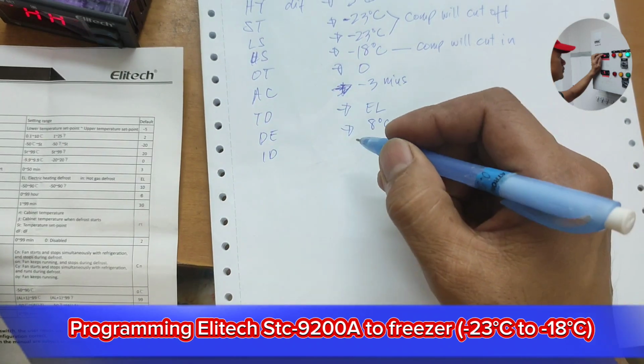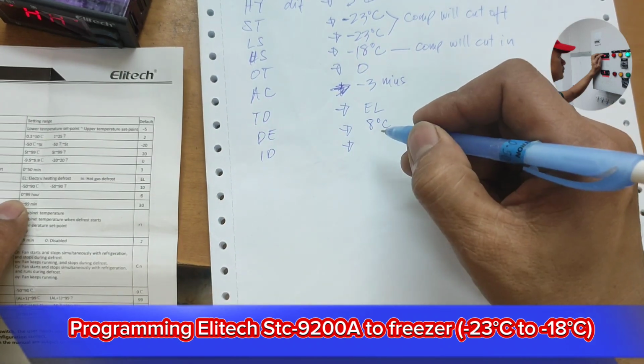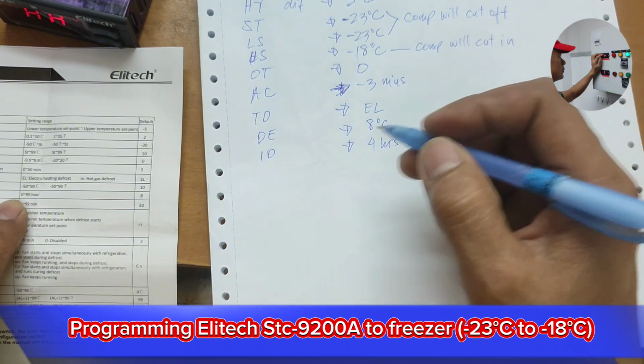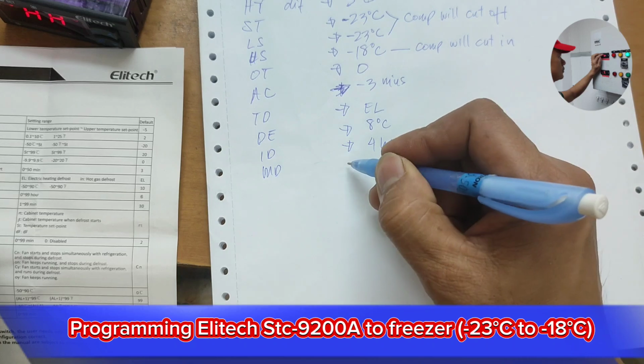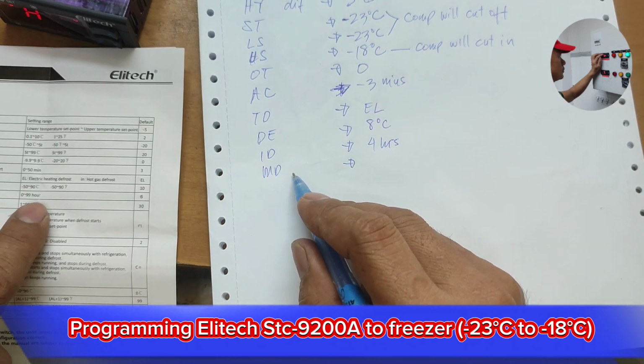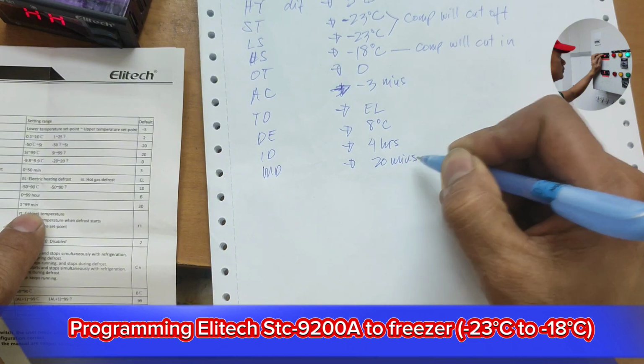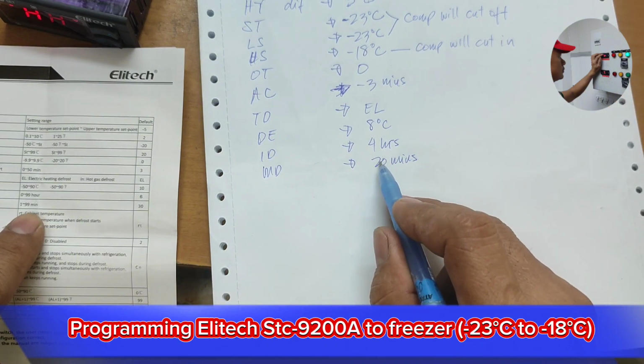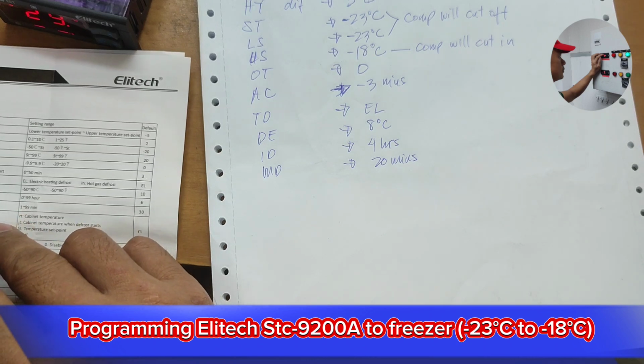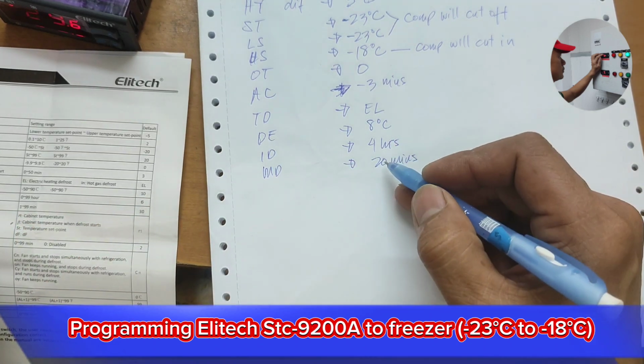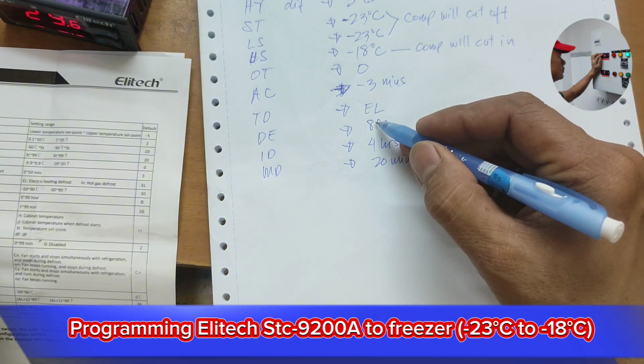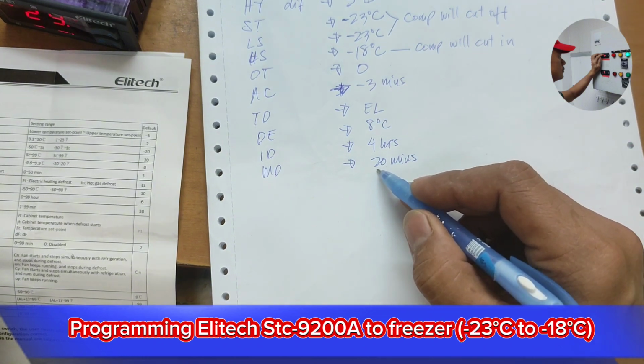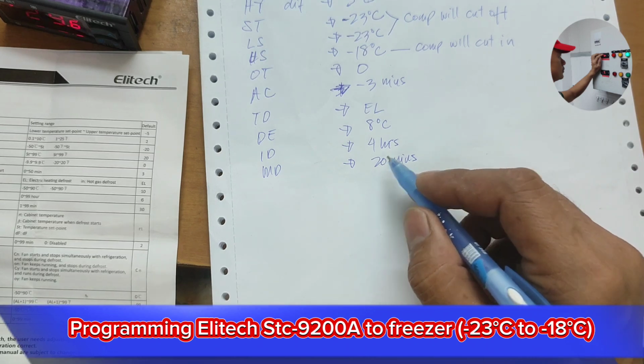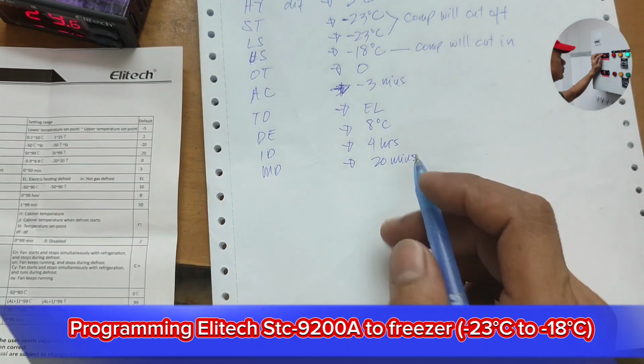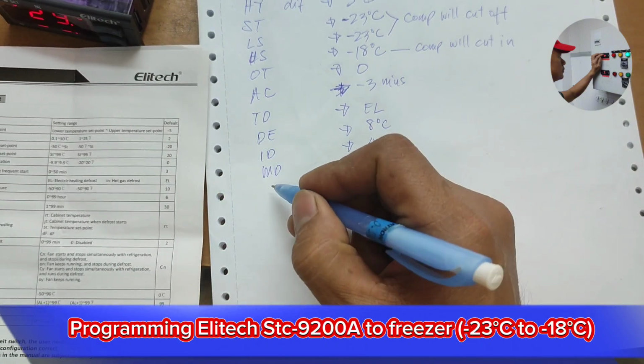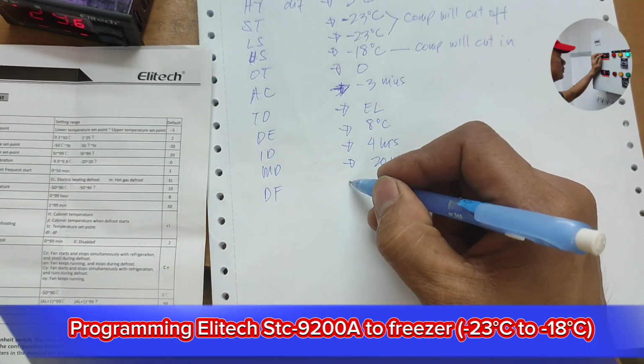And our ID, the defrost cycle, we set that to every 4 hours, it will automatically defrost. And the MD is the length of defrost, we set that to 20 minutes. But don't worry, the 20 minutes will not happen once the defrost stop temperature is reached. Once the sensor of the evaporator senses that it's already 8 degrees Celsius, it will cut. So it doesn't matter how many minutes you put here, as long as the evaporator sensor is active.